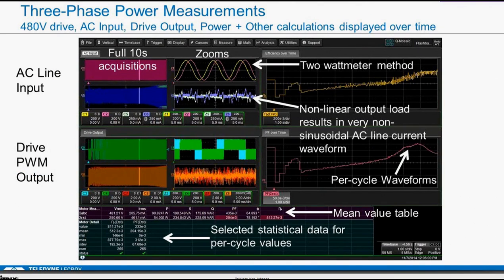Okay, just two more slides, and then we'll go to Q&A. This is just an example of bringing everything together. This is a three-phase 480-volt drive. It has an AC input from the line, and it has a drive output, which is PWM. And then I'm using a 2-wattmeter method. I've got 8 inputs on my oscilloscope that makes the power measurements. So I've got 4 for the line input, 4 for the drive output. And then I'm calculating these various mean power quantities here.